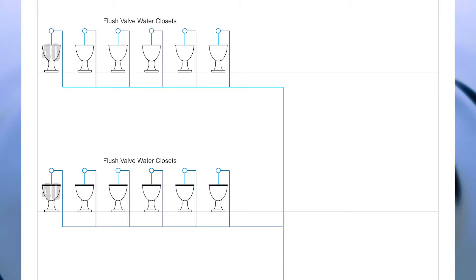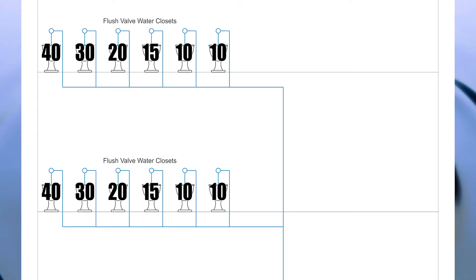Starting on the left-hand side we have 40 fixture units, 30, 20, 15, 10, and 10. So that means the fixture unit load on both stories — on this pipe here and on this pipe here — will be 125 fixture units each.